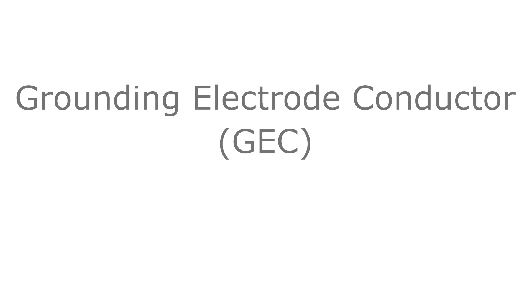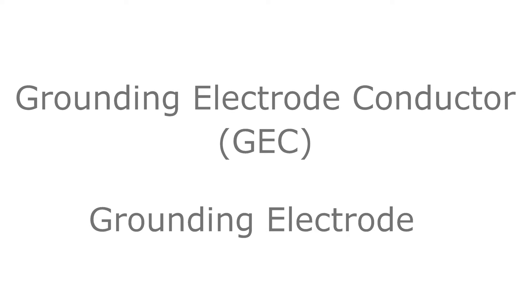There are two main components to the AC grounding electrode system. The first is the grounding electrode conductor, or GEC. This conductor is used to connect the grounding electrode to the equipment grounding conductor, or to the grounded conductor of the circuit at the service equipment. The second is the grounding electrode. This is a conductor, like a rod, pipe, or plate, in direct contact with the earth. Its purpose is to provide a low impedance connection to the earth.